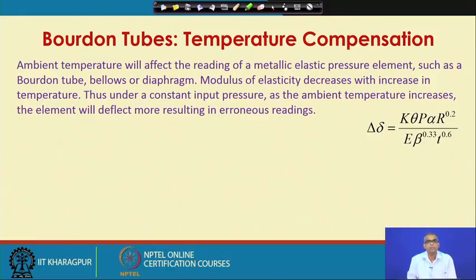We have discussed that Bourdon tube deflection depends on the modulus of elasticity. If you remember, the displacement of the tip of the Bourdon tube is inversely proportional to the modulus of elasticity. Now, we know that modulus of elasticity changes with change in temperature. In fact, for most of the materials, modulus of elasticity decreases with increase in temperature. So, if modulus of elasticity decreases for the Bourdon tube material, the Bourdon tube will now show more deflection for the same pressure. So, it will cause an error in the reading. So, we need to compensate for the effect of ambient temperature change.